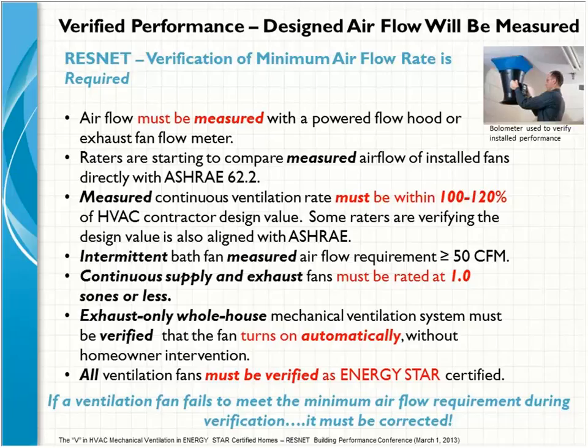100%, of course, because that's the minimum and you have to meet code. But we don't want to go too far over. We don't want to take the Tim Taylor approach and go, well, if 100 is good, 150 or 200 is even better. We want to keep it within 20% above, because we don't want to be wasting energy to overventilate the home, and we could create conditions within the home that are uncomfortable by overdrying as well.